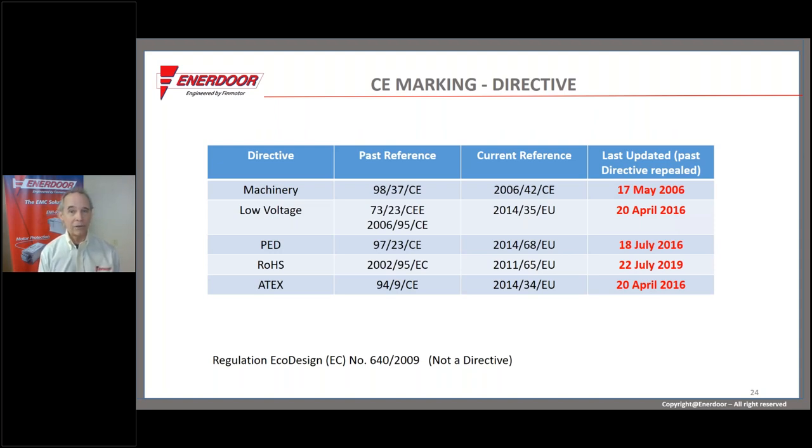The formality is quite different. In Europe, under the machinery directive, there is a legal obligation to write down, assess, and recognize every hazard your equipment has, and to justify your design approach as one that's safe enough. Like the EMC directive, the requirements in the machinery directive are outcome-based. Under EMC: don't cause interference and don't be interfered with. Under the machinery directive, Annex 1 lists 60 different ways machines can hurt people, and the requirement is that the machine not hurt any reasonable person.